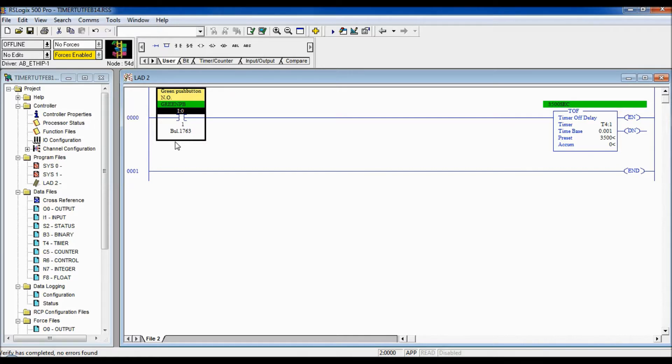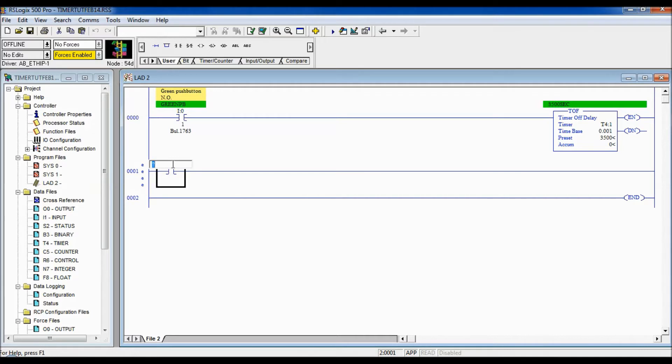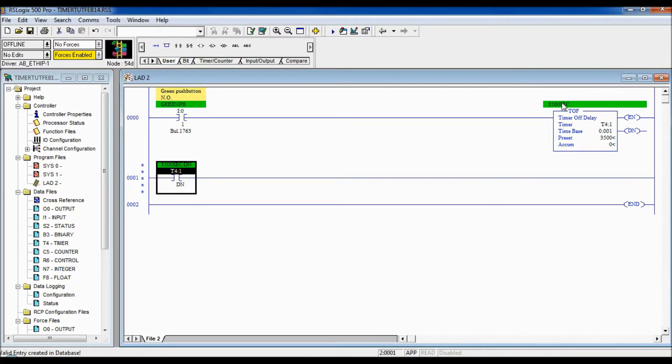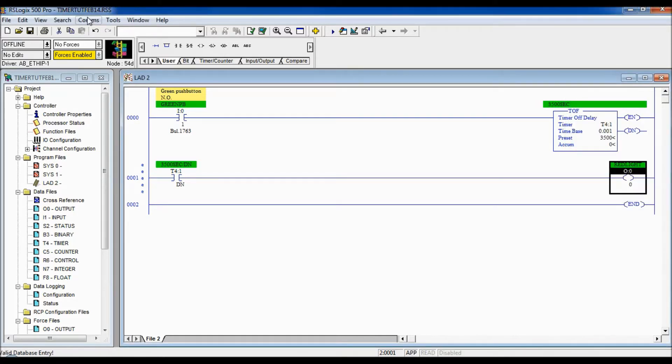The way it's set up now, when the green push button is pressed it will begin timing. Let's add more logic using the Done bit associated with T4:1 to see what happens. We address it to T4:1 with the DN bit, and you can see the name matches this timer.